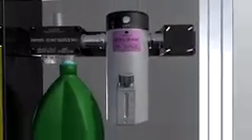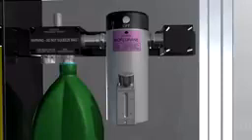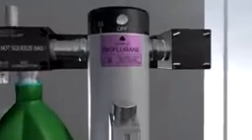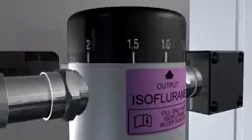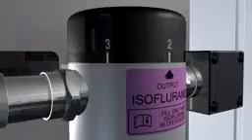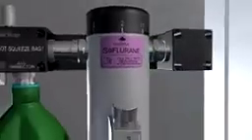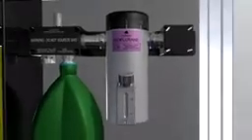The low-resistance draw-over vaporizer adds volatile agent to the carrier gas passing through it. Volatile agent is added by using the selector wheel to achieve the desired percentage. We now have an anesthetic gas comprising oxygen, volatile agent, and a variable amount of room air.